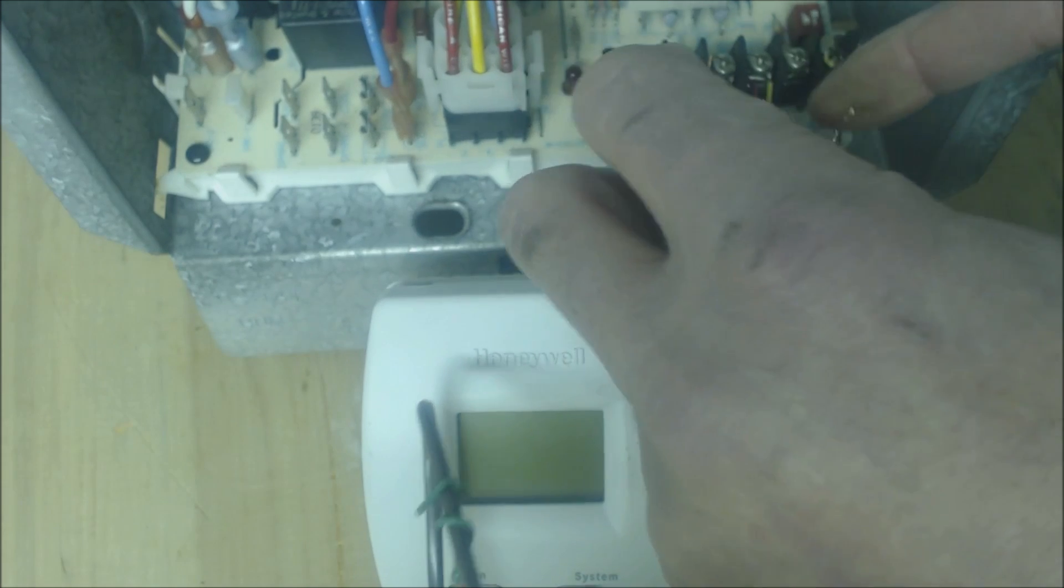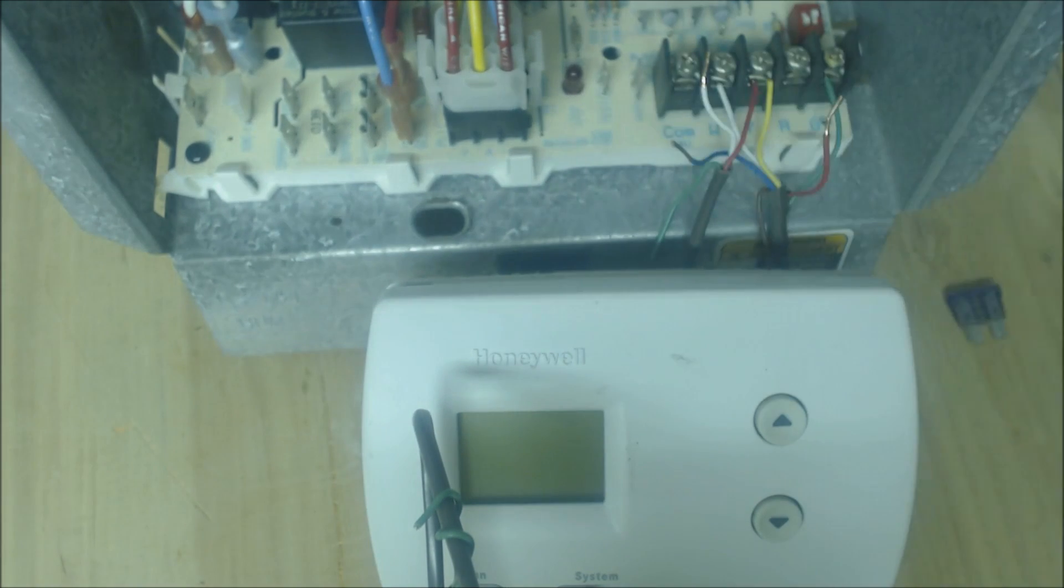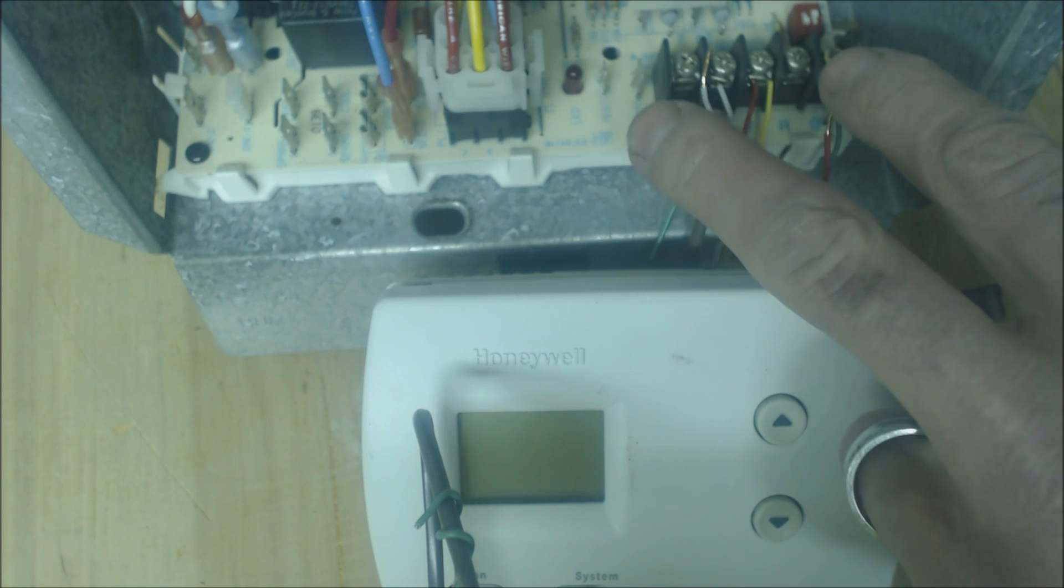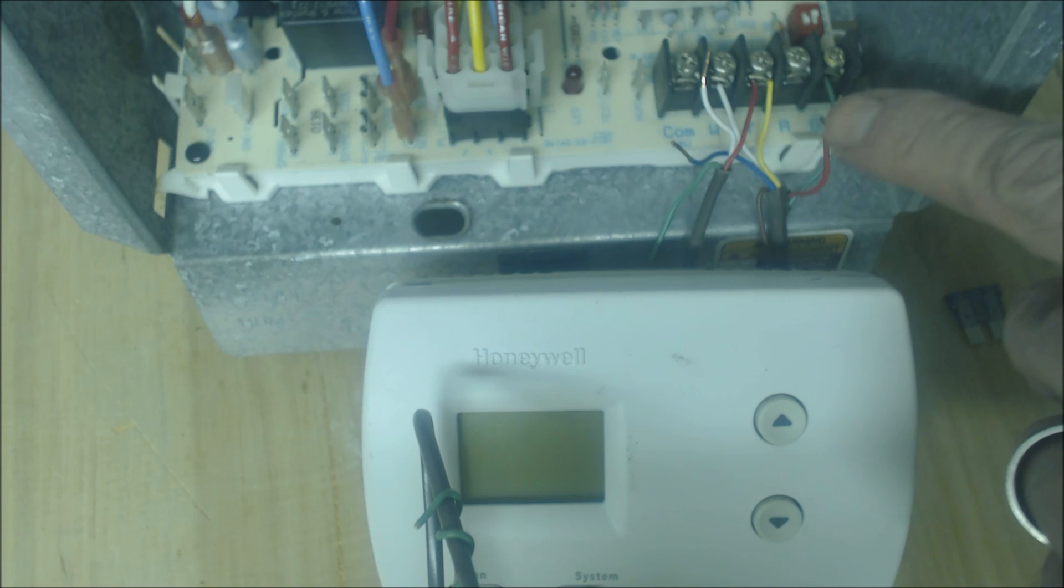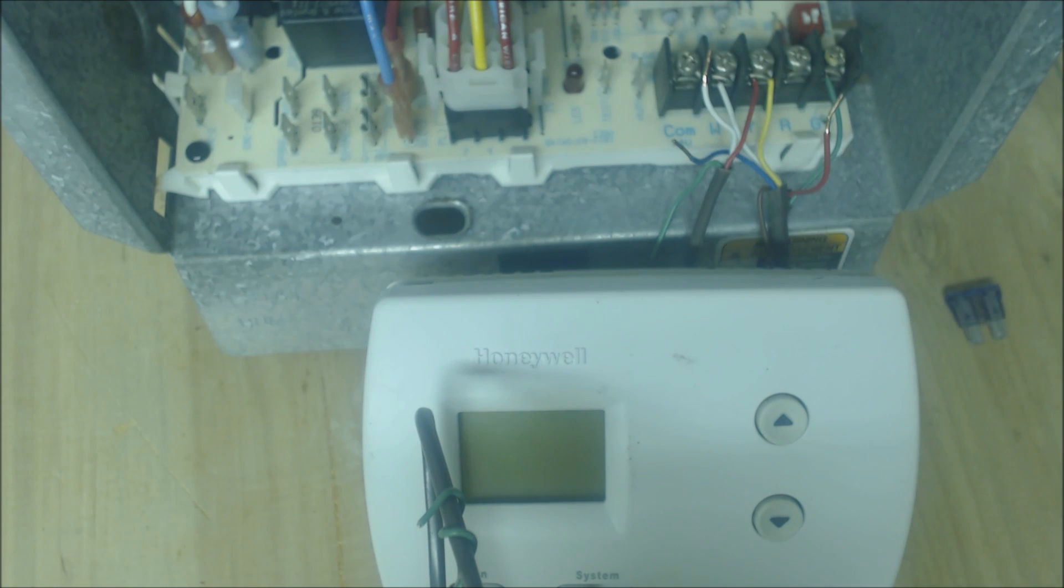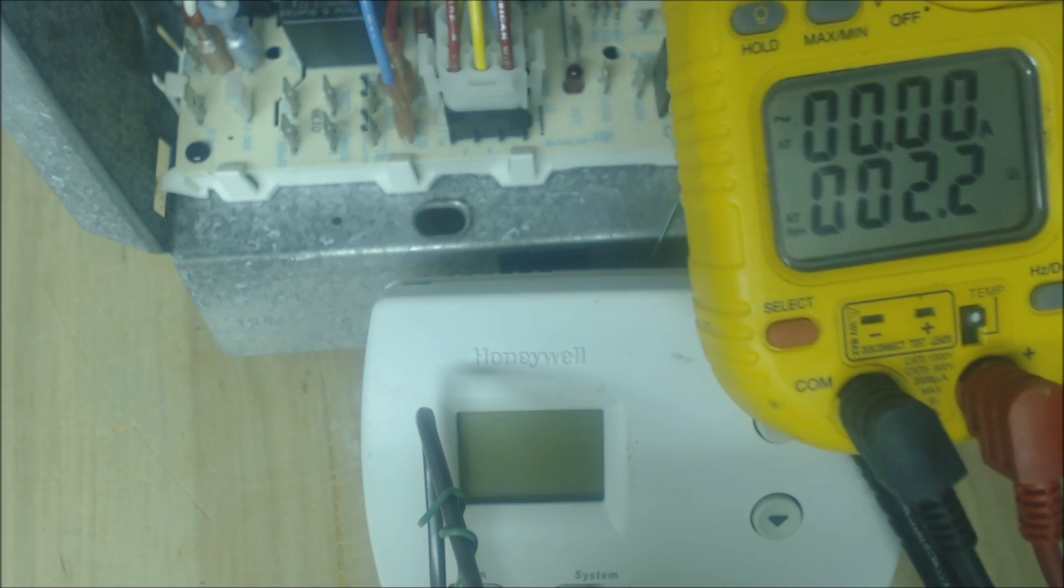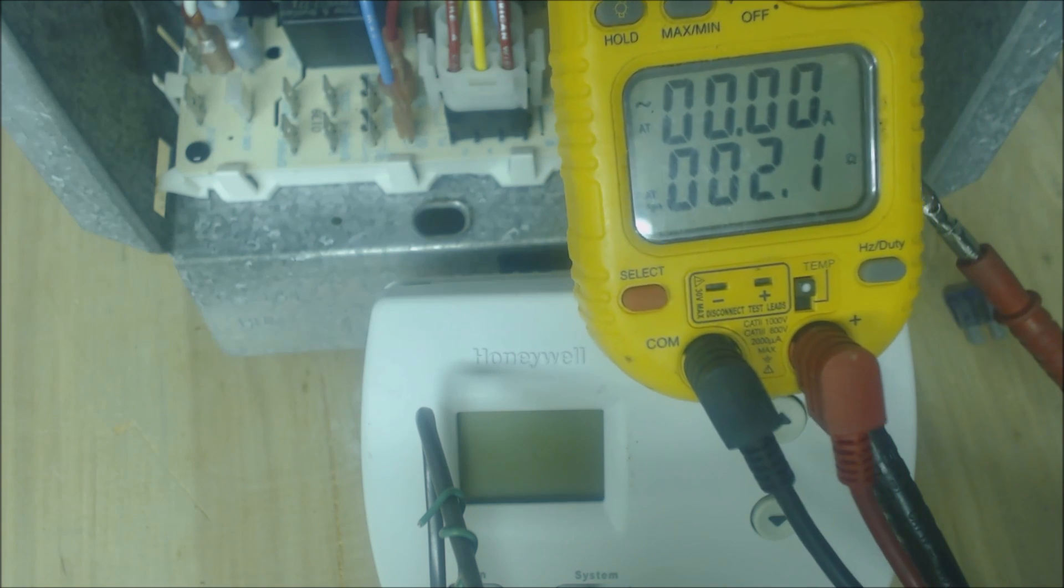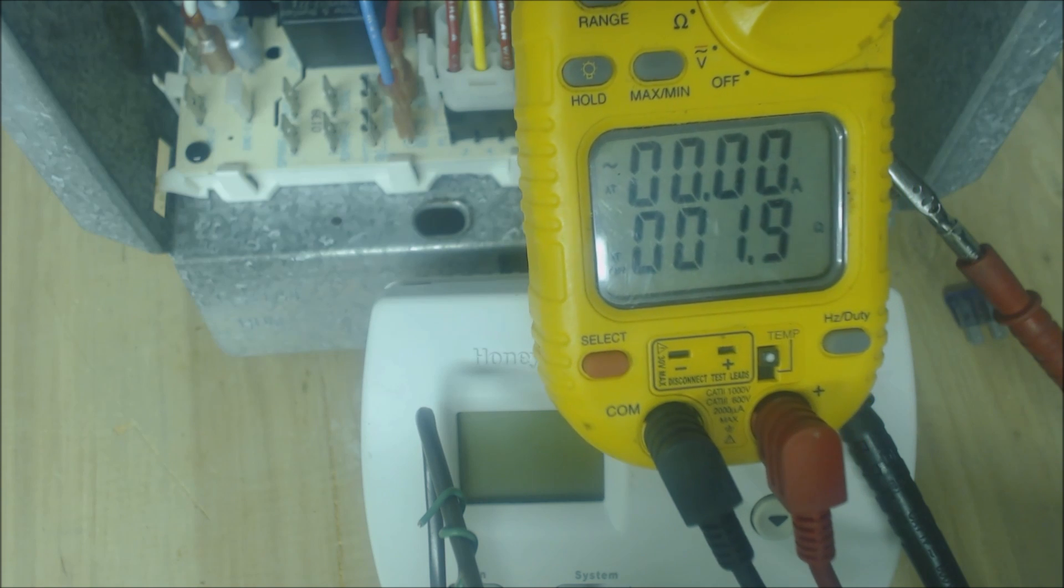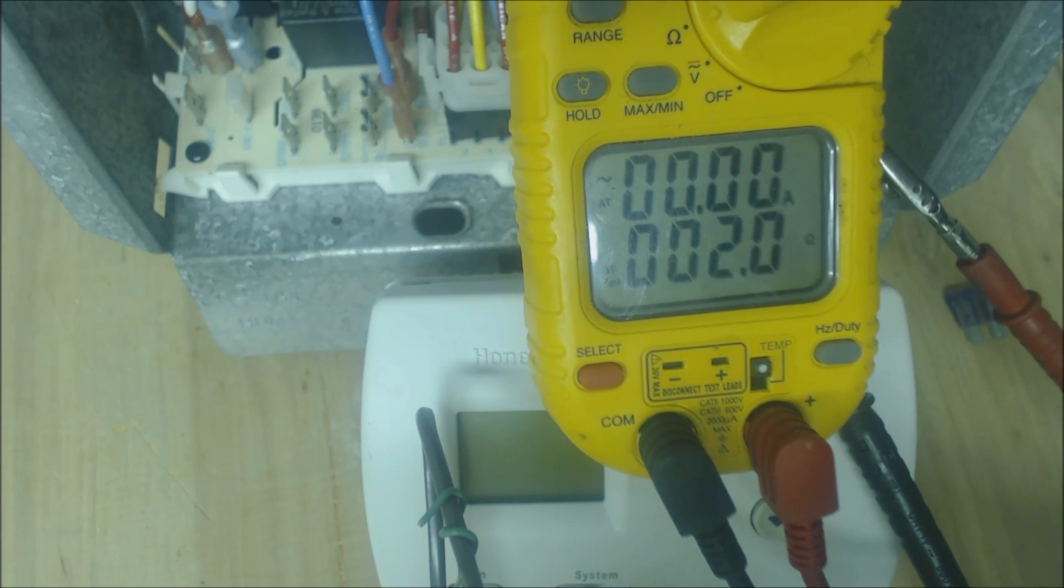Now that we have these wires out, we're going to check to see if we have any type of resistance. If we do have resistance between this blue wire and this red wire that we connected to common and red, then that would be a problem. So we're going to go ahead and connect them. You see that we have 2.1 ohms of resistance, so that's not good. Those wires are touching somewhere.